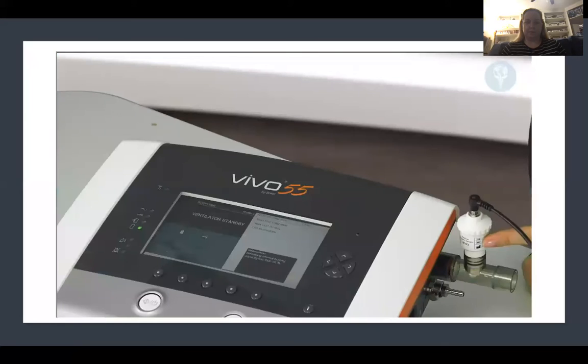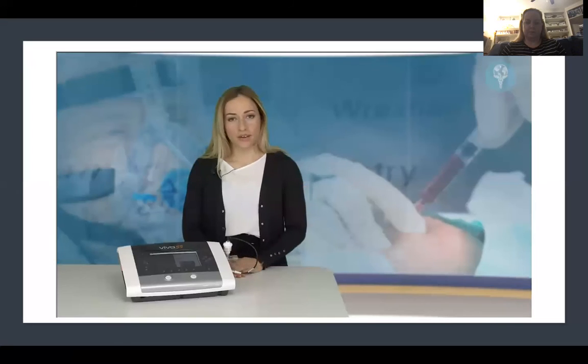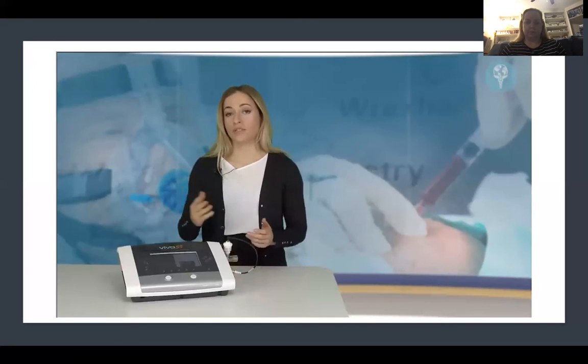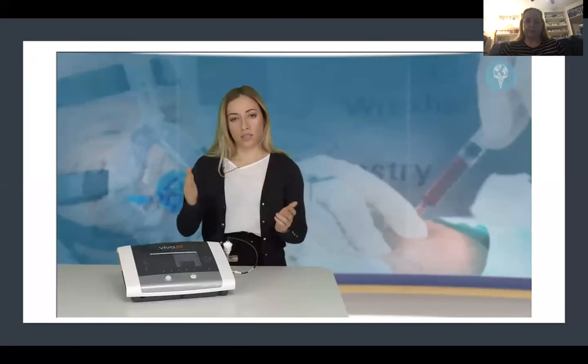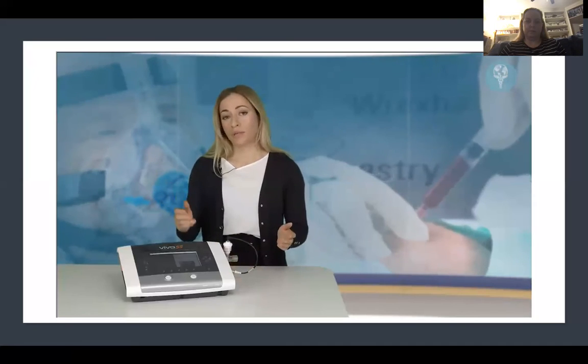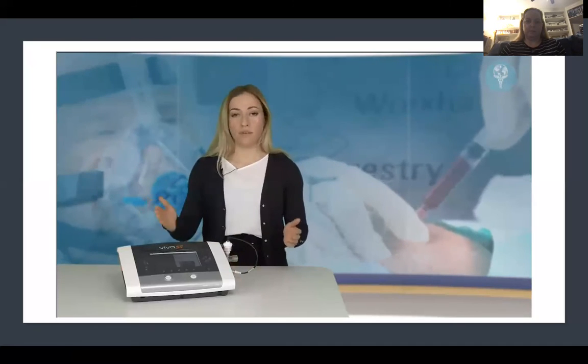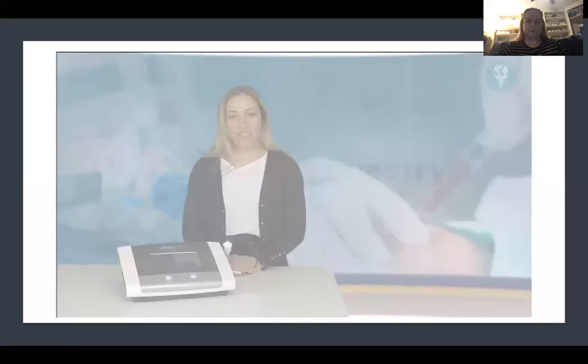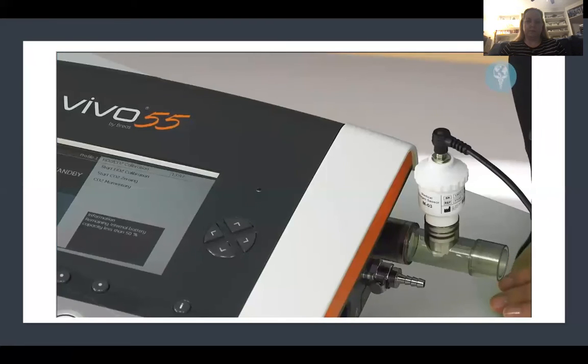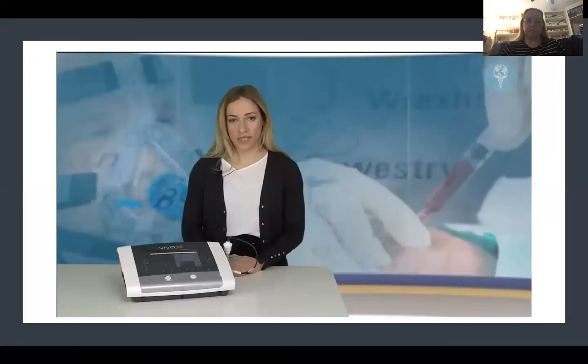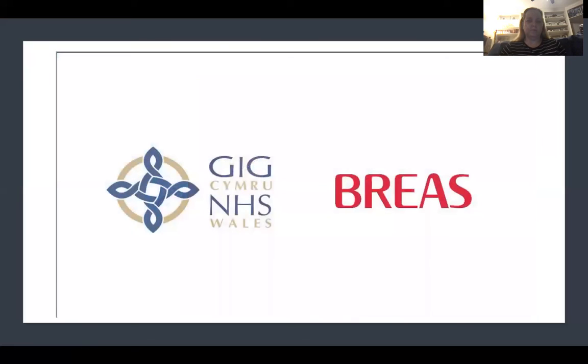The sensor module on the side here will need changing roughly every 6 months. One thing that's important to note when entraining oxygen through the Vivo 55 is that you should only be entraining oxygen while the device is actually running and ventilating. So make sure that you start the treatment first on the ventilator, then turn on your oxygen. When you want to stop treatment, turn off the oxygen before stopping treatment on the ventilator. In summary, we've just covered how to set up the FiO2 sensor, so you'll now be able to monitor the fraction of inspired oxygen that you're delivering to your patients.